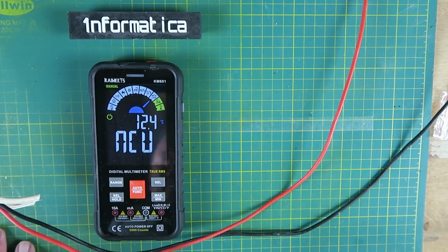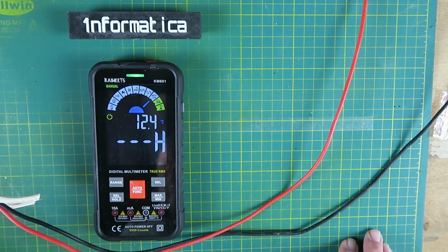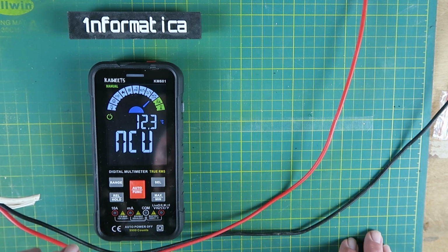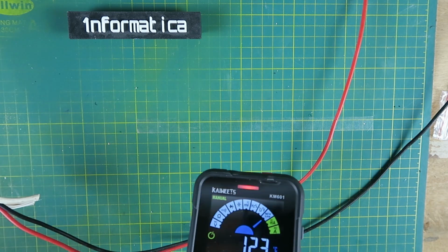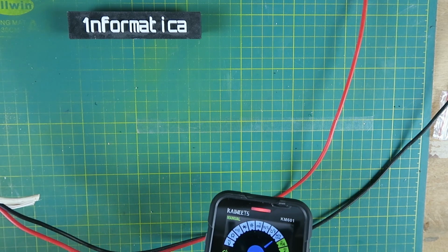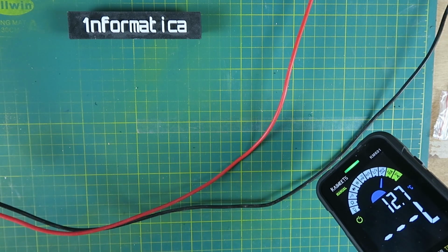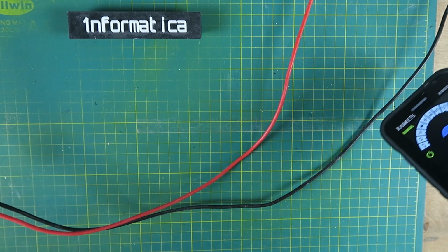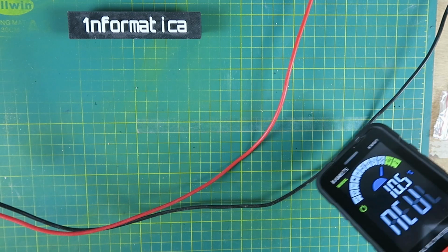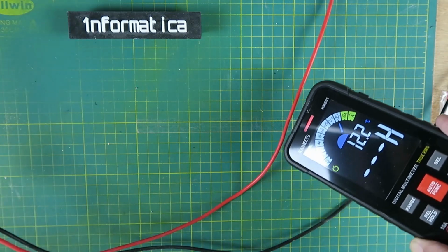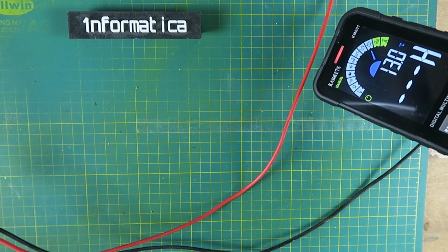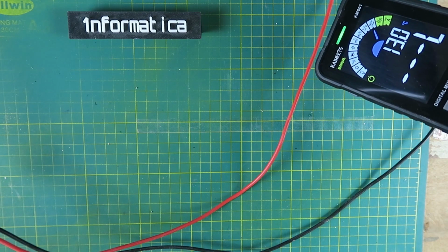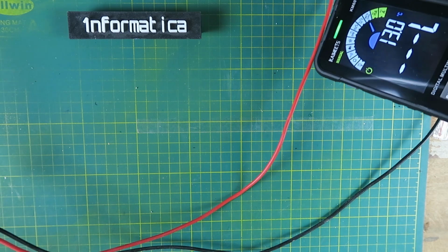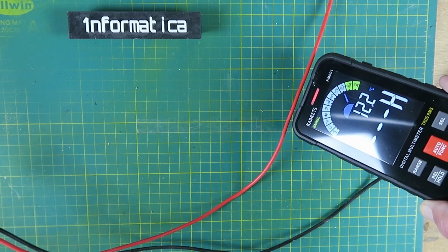On the NCV range then, now please don't try this at home. I'm going to make these wires live, which I have just done, and you saw the meter briefly detect something. If I bring it near to the wires now, we can see the red light has come on, which is indicating a high voltage. If I bring it near to the black wire, it's showing a green and an L for the low voltage. That should then be the neutral wire. As I now move it along the wire, see at that point there it's dropped to a low voltage, and then to a high voltage.